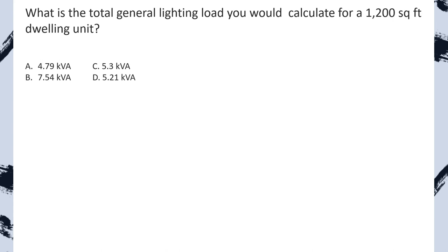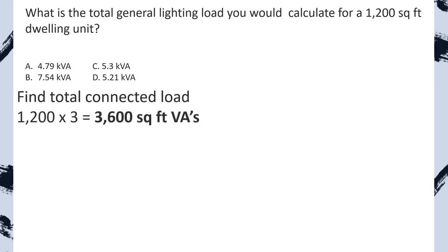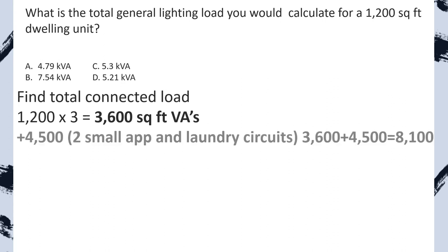What is the total general lighting load you would calculate for a 1,200 square foot dwelling unit? Notice I took out all the pointers from the previous slide. Anytime it asks for the total, you're always going to be applying a demand factor if there is one, and in every one of these calculations you're going to have the two small appliance and one laundry circuit. Step one, find the total connected load: 1,200 square feet multiplied by three VAs per square foot gives us 3,600 VAs. Now we tack on 4,500 for the two small appliance and one laundry circuit — 3,600 plus 4,500 equals 8,100.